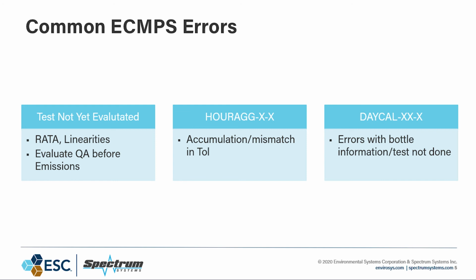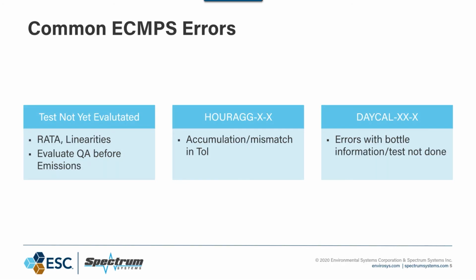If a specific parameter within Stack Vision that is a time online parameter is blank, missing, or invalid, it can cause a miscalculation between what's being calculated and what's being reported, so you'll sometimes get a mismatch. That's another common error that we see quite a bit.